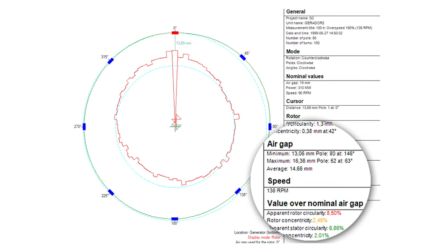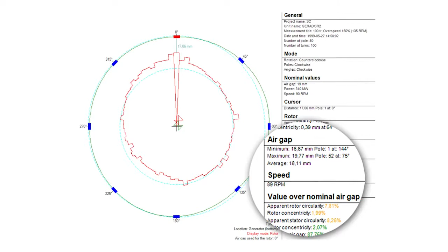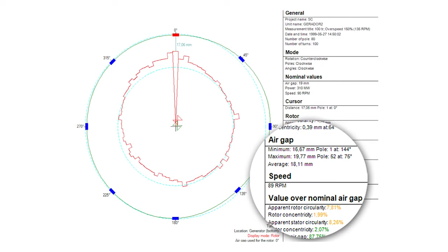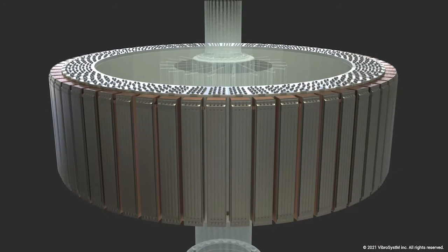And in addition, we could see that the rotor shape, the rotor circularity, was very high, in fact beyond critical. And again, that's also to be expected because that's the design of the rotor. The rotor is moving, it's distorting to absorb the centrifugal forces, so you expect to see a shape that is distorted. And as they slow the unit down, you can see the air gap increase because the rotor is slowly shrinking in size. There's less and less centrifugal forces, so the rotor is decreasing in size. And also, it's moving less and less. So the rotor circularity, its rotor shape, was also improving. If you look at the initial results, everything looked like the unit performed as designed. Everybody thought that the rotor rim was doing what it was supposed to.